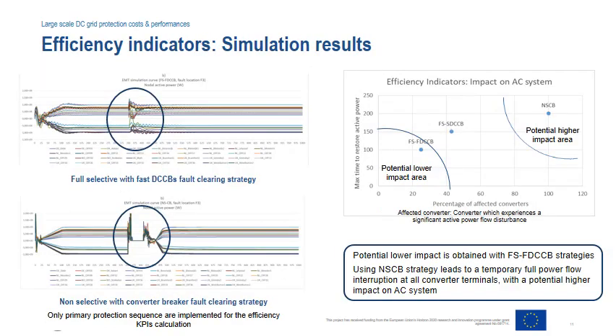Impact on AC system stability is a key driver for the design and selection of the protection system. From this perspective, the performance of a protection strategy can be assessed through the time it takes to restore active power through the DC grid. This time has been calculated through EMT simulation for the two fully selective protection strategies and for the non-selective with converter breaker strategy. The figure on the left shows an example of the trajectory of the active power at all AC-DC converter terminals during the protection and grid restoration process.